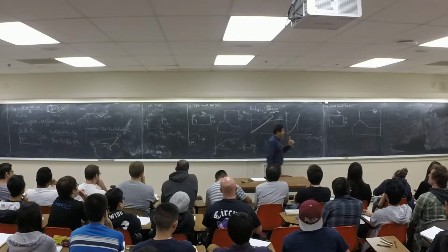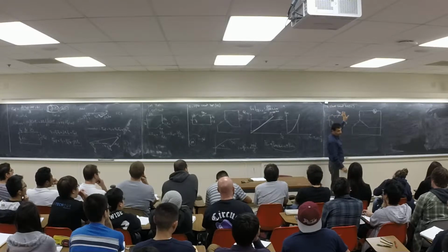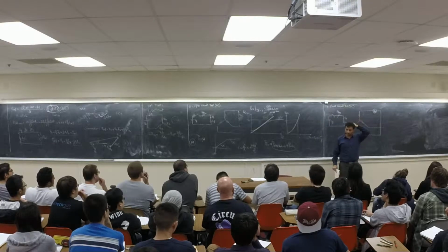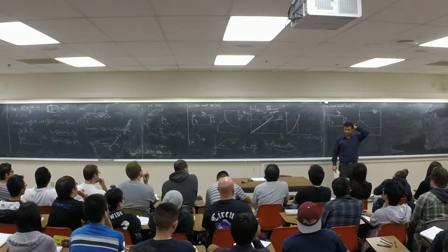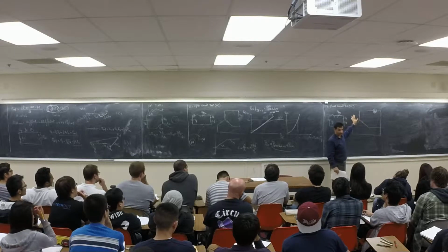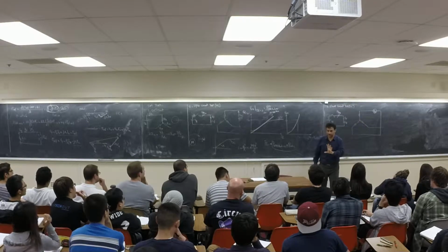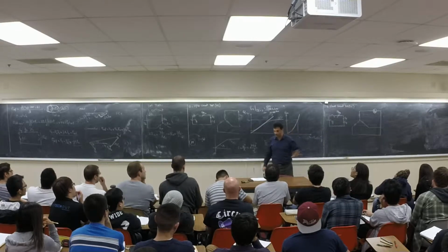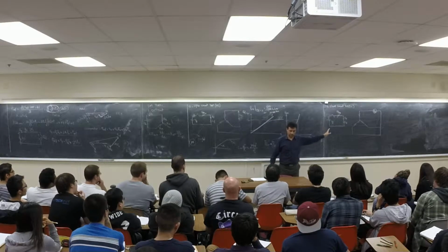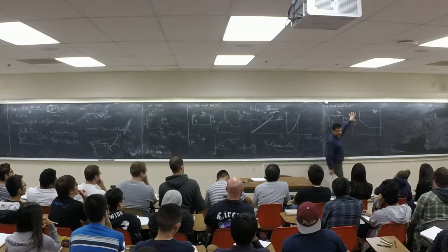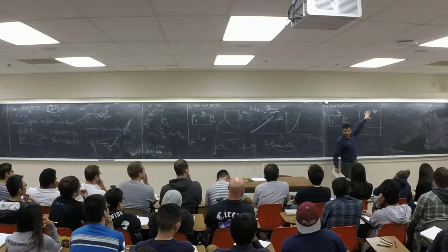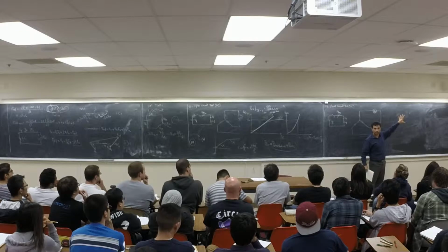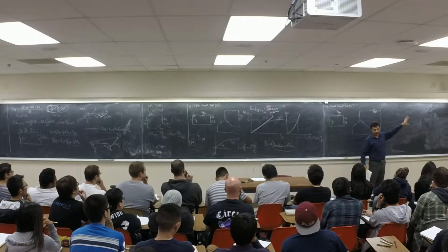If you don't put a big resistor here, what's going to happen? The machine is rotating at synchronous speed, right? And you generate a big voltage, like a rated voltage. Think about it. I mean, not 10 times or 20 times the rated voltage, but for example, rated voltage. If you have a rated voltage here, right, and it's shorted, you're going to see a huge current, right? You're going to kill the machine.